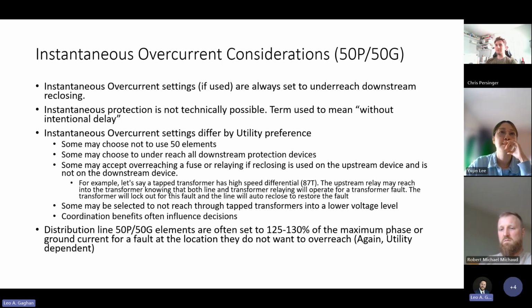Right, there is some risk there. If the system gets stronger and it begins to overreach with time, you could overreach something that you didn't think you were going to overreach, and then you're going to miscoordinate, and more people will lose power than what you want. Some may choose to underreach all downstream protective devices with or without reclosing. And then some may accept overreaching a fuse or relaying if reclosing is used on the upstream device and is not on the downstream device.